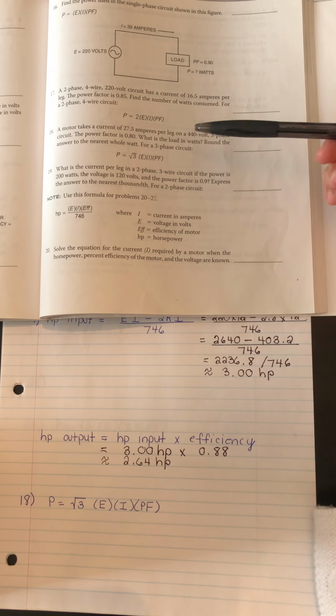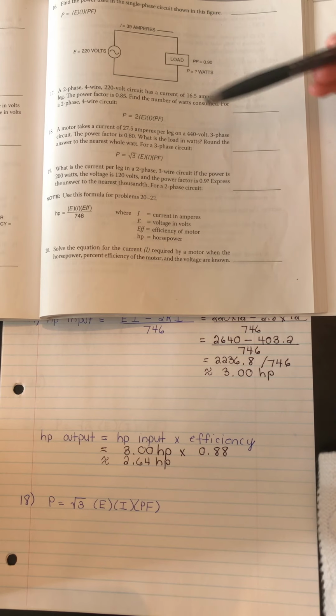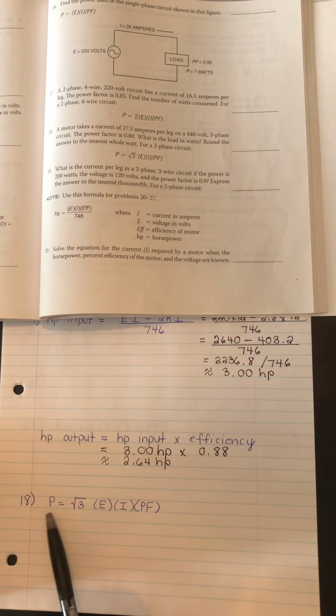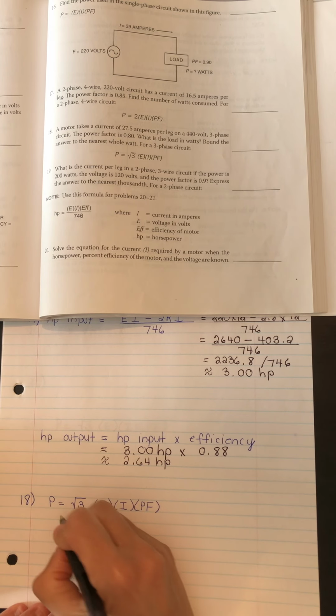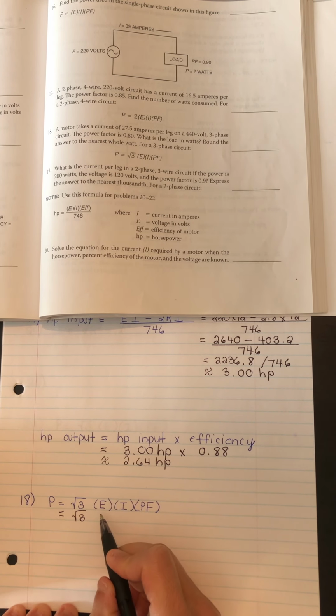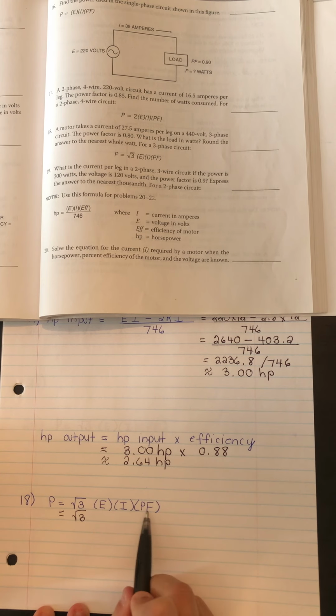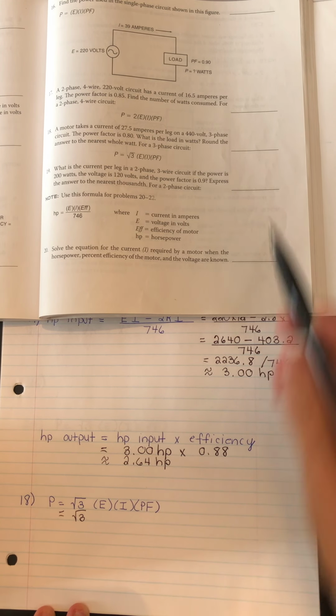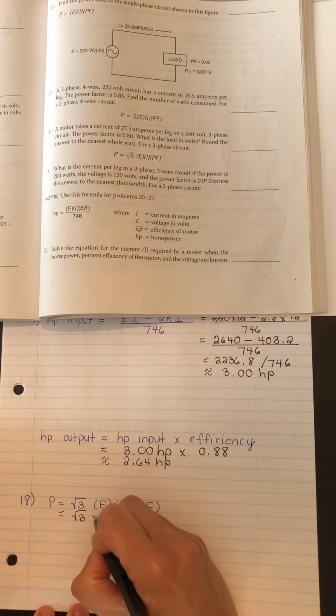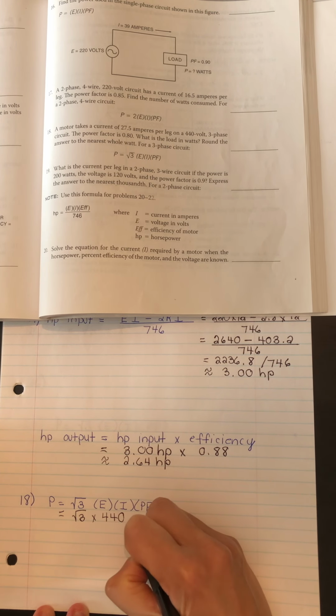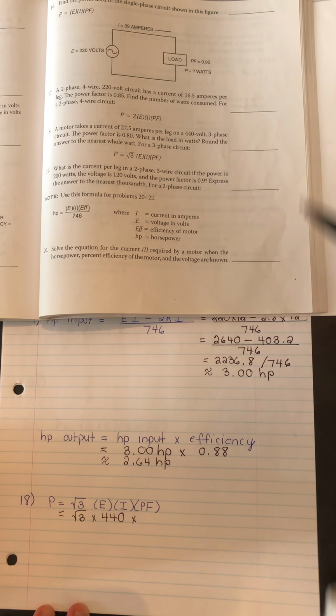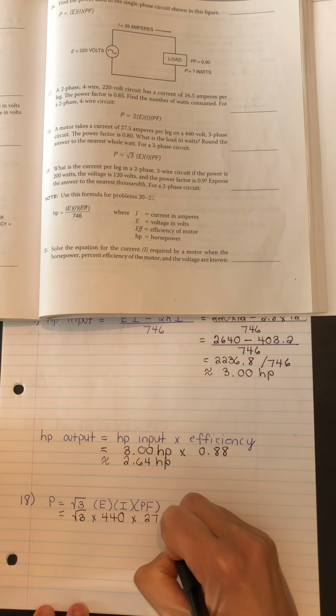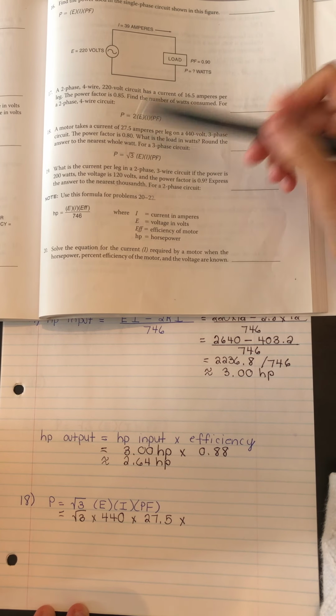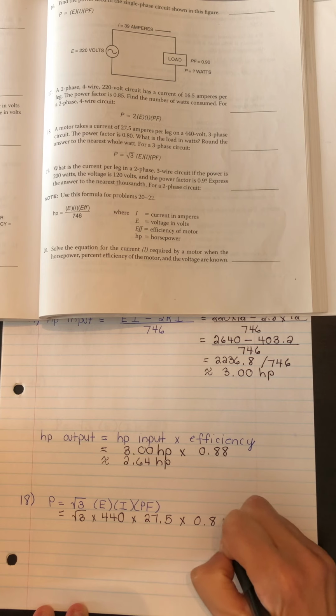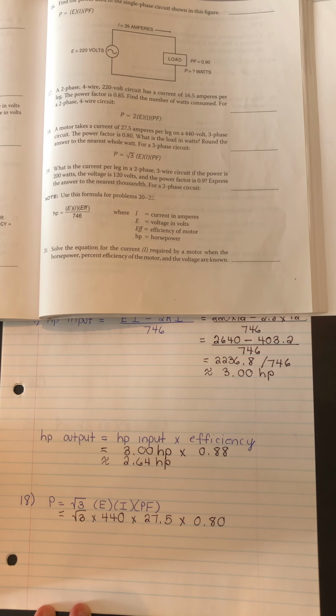So the equation is given and we're asked what is the load in watts. So we're solving for power here. It's already isolated. So we simply will be substituting, and implied here is multiplication throughout. So we have to substitute 440 for the voltage. For the current, we're substituting 27.5. And for the power factor, this 80%, 0.8. Okay, and you just can multiply all of those quantities together.